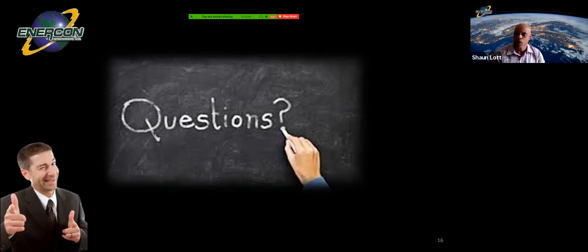Wow, 40%. So are there ways to decrease the financial impact for EMI protection? Sure. One of the things that is very helpful when you're taking on a program that has EMI requirements is knowing those requirements up front. If you know the requirements up front, you can set up the way that your system is designed to cluster your devices that need the most protection together in a certain area, and then cluster the ones that need less in another area. By doing that, you can provide less protection to the pieces that need less protection, and that's of course cheaper. You don't have to put as much in line, and then you provide the higher level of protection only to those devices that you need, and we call that a zoned way to do this.